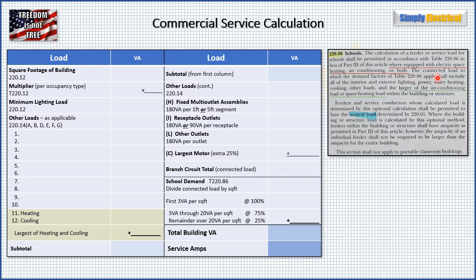It goes on to say the connected load to which the demand factors of Table 220.86 apply shall include all of the interior and exterior lighting, power, water heating, cooking, other loads, and the larger of the air conditioning load or space heating load within the building. So we're going with the connected load of basically everything in the building, and the only exception is we're taking the larger of the air conditioning or space heating — leaving the lesser of those two out, but taking everything else.